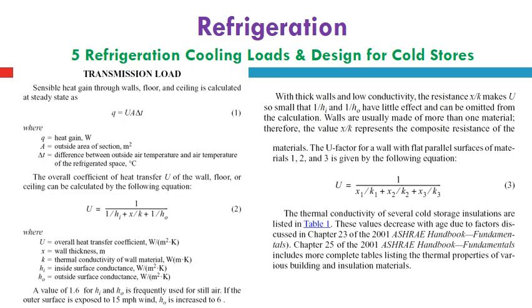Firstly, we will go through the first load component, which is transmission load. Transmission load, sensible heat gain through wall, floors, and ceiling is calculated as a steady state as Q equals U A delta T, where Q is the heat gain in watt, A is the outside area of the section to be calculated, across which the heat will be transferred, in meter square.